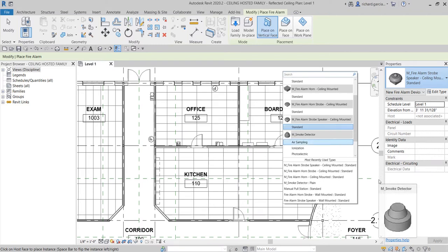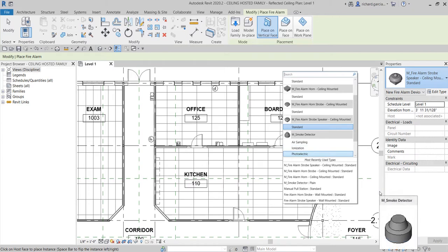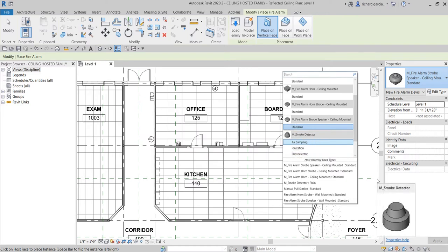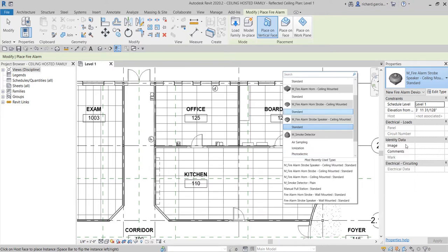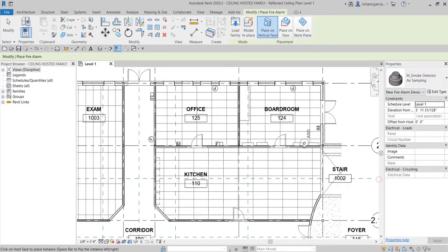You'll see different types of smoke detectors, but the 3D models are essentially the same — just different names. In Revit, you don't need to create too much detail in your family model. One important thing: don't forget to add a connector to your family so you can create a circuit or system. For fire alarm devices, keep the 3D model simple.